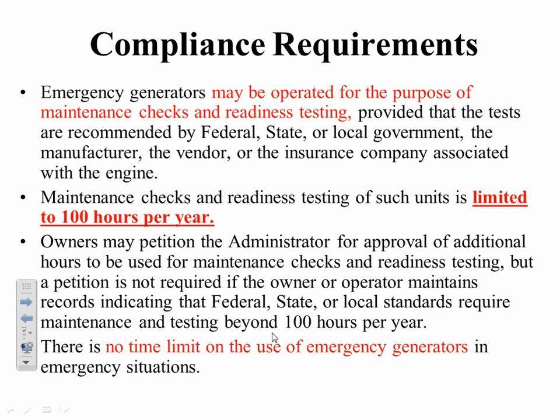And here, I highlighted this: emergency stationary internal combustion engine means any engine whose operation is limited to emergency situations, like we just described. And the pumps are brought in here. That's the way it's worded. Compliance requirements. Okay, now that we've defined it, what are the requirements? Emergency generators may be operated for the purpose of maintenance checks or readiness testing, or in our case, in the facility we're going to design commercially, exercise period for the generator set. Those maintenance checks are limited to 100 hours per year for an emergency generator.